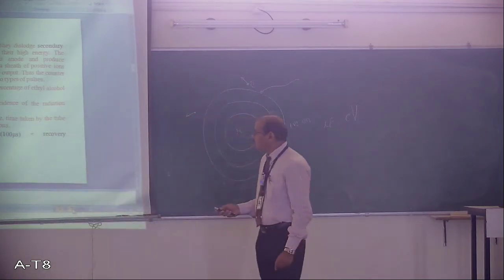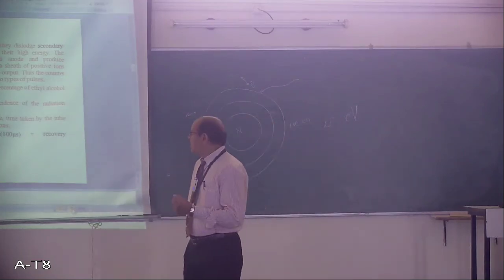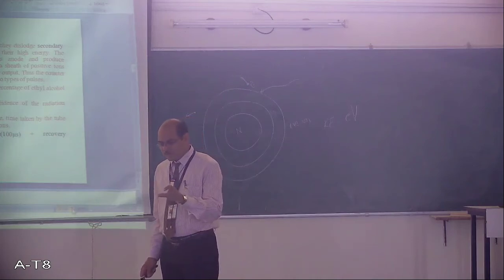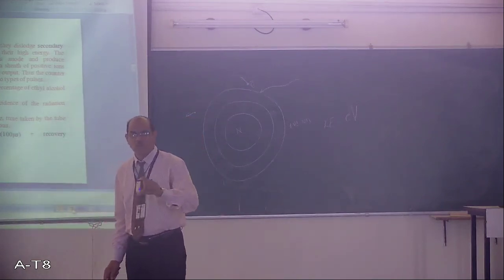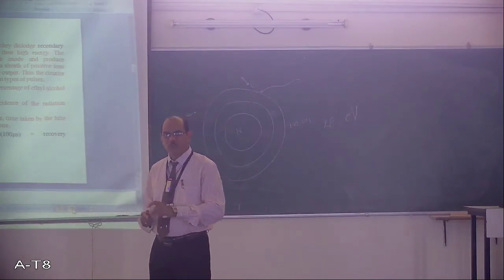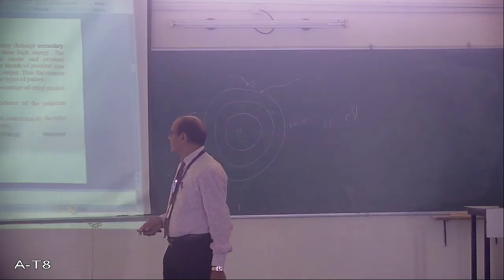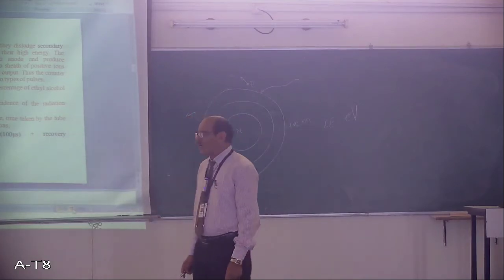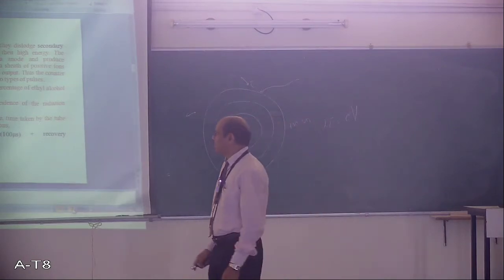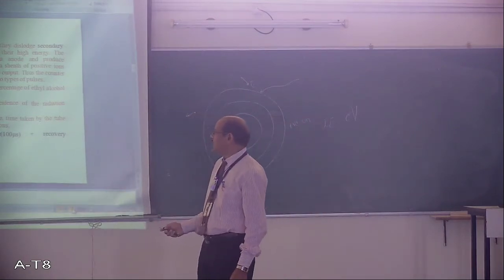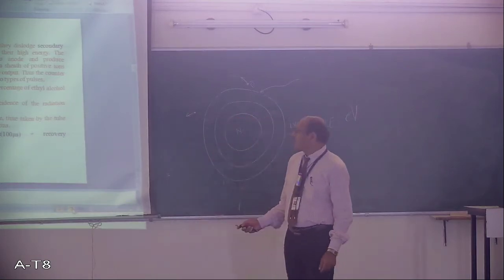Now after the dead time comes the recovery time. It means that from the dead mode to the active mode, the tube has to activate again, and this takes a certain time, called the recovery time. Recovery time is of the order of 100 microseconds. Dead time is also of the order of 100 microseconds. The sum of these two, dead time and recovery time together, is called the paralysis time.